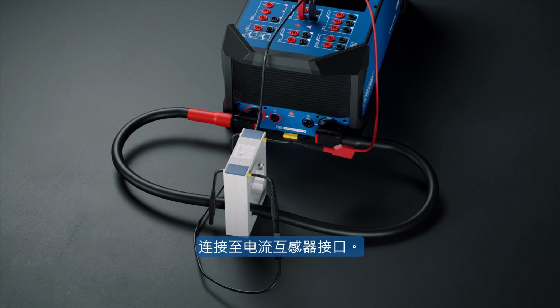To minimize the influence of cables and contacts when testing CTs, always make sure to use the 4-wire method to ensure reliable measurement results. Additionally, also remember that unused cores must be shorted in CT testing. After connecting to the current transformer, the device can be put into active mode and the test can be started with a slide on the touchscreen. As you can see, this can even be done with gloves. Ratio tests can be performed up to 1000 amps, which allows for testing up to nominal currents in many instances.